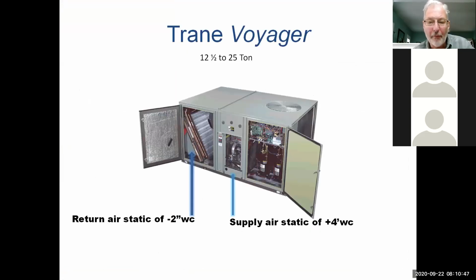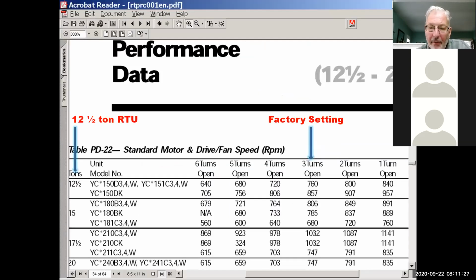So if you look at a Voyager, Voyager is pretty easy to get static pressure on. If you drill a hole in the blower door, excuse me, to get the return static, do it with the door open, don't drill into the tubing. But in this area right here, if you can get a static pressure in this area through the door, and then right underneath the burner, that's actually part of the plenum. If you drill in right here, you should be able to get a static pressure reading for the supply. So you can get your static. If you can't get it at the return ducts, you can do it from the rooftop. And those are the two places that you want to take a look at. So we add them together, and look at a couple other things before we get into it.